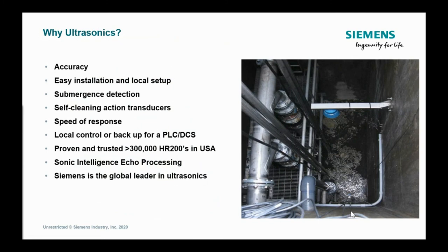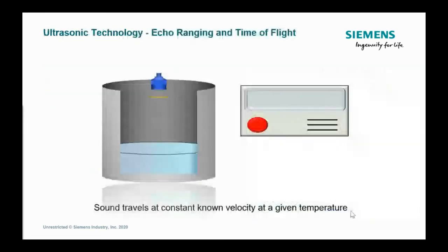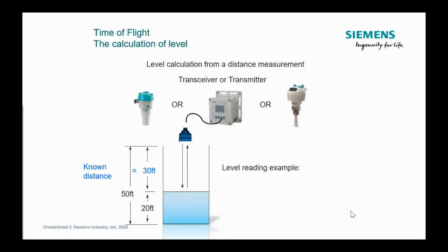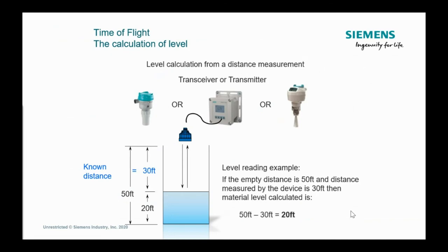But let's set a foundation here for just how ultrasonics works. It works on a principle of time of flight. It's going to emit a pulse. It's going to measure the time that it takes to reflect off some surface and come back. And it's the old fourth grade or fifth grade math, right? Rate times time equals distance. The rate is the speed of sound. The time is measured, and from there it can calculate a distance. If you know the distance to the material, you can figure out what the level in the tank is. If you know, in this case, the bottom of your tank is 50 feet, and you measure a distance of 30 feet, then you can figure out there's 20 feet of material in the tank.